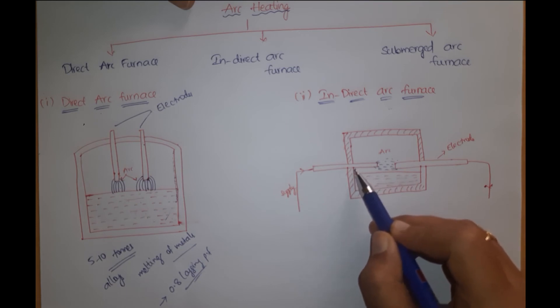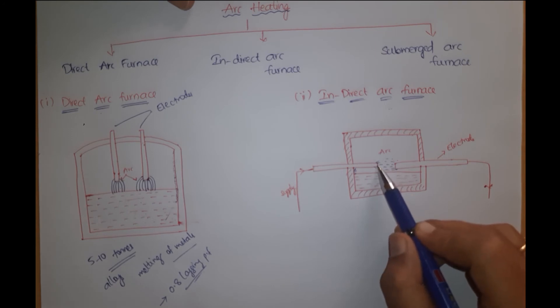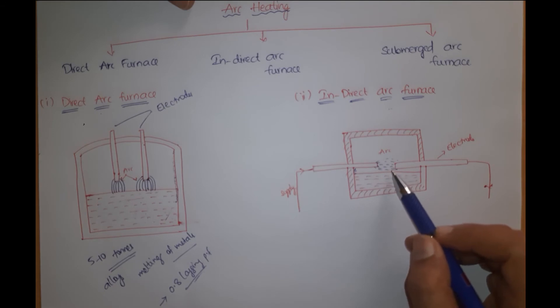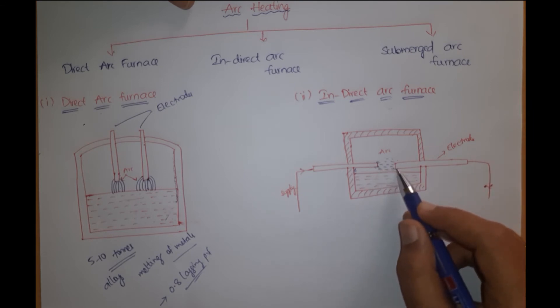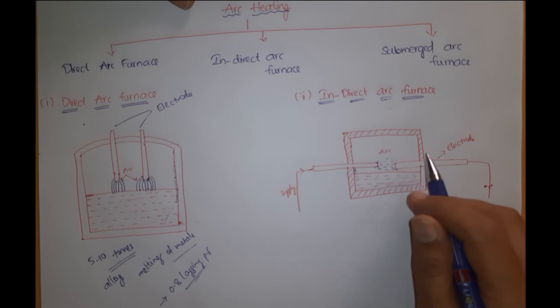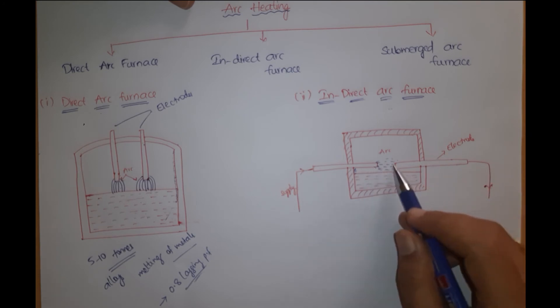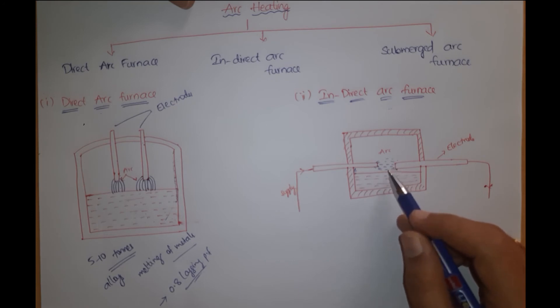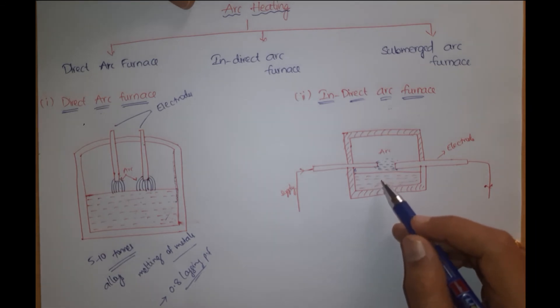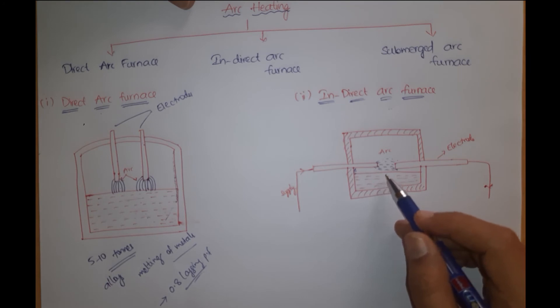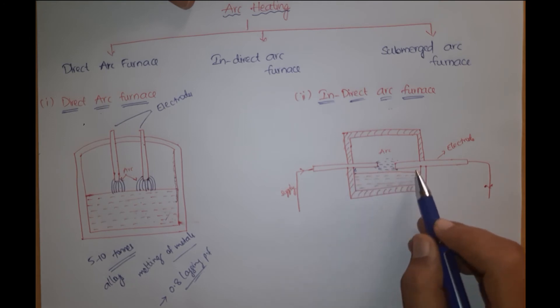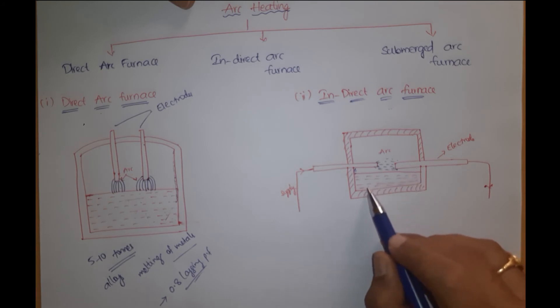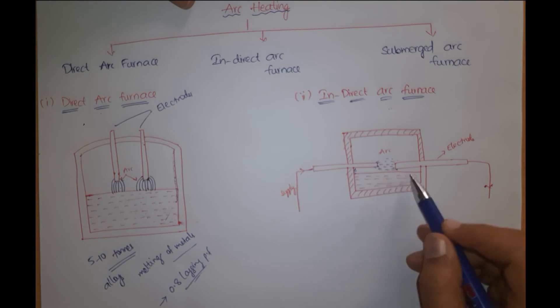By short-circuiting the electrodes manually or automatically, we can produce an arc between the electrodes. The heat from the arc and the refractory lining is transferred to the top layer of the charge. The arc may be produced directly by applying high voltage, or indirectly by contacting the electrodes, supplying low voltage, and then pulling them apart. Heat is produced due to I²R losses of the arc. As there is no current passing through the body of the charge, there is no stirring action, so only the top layer gets heated and there is irregular temperature distribution.